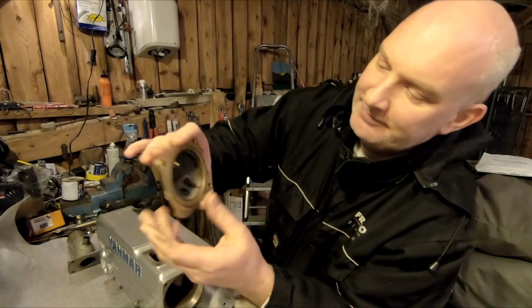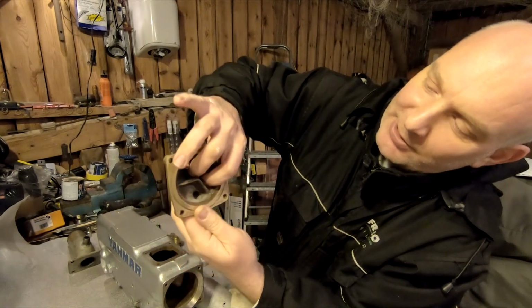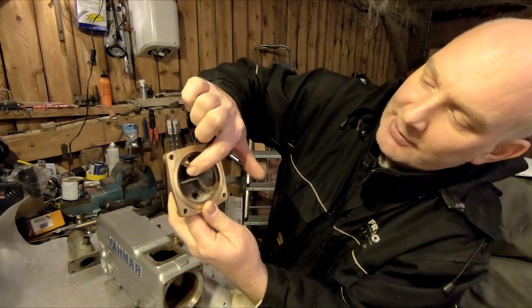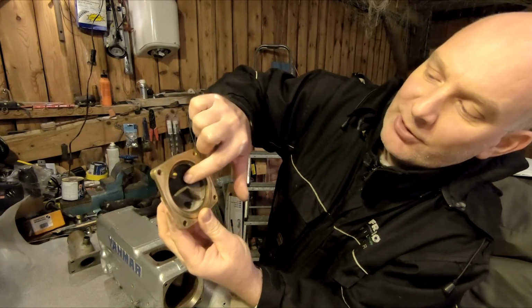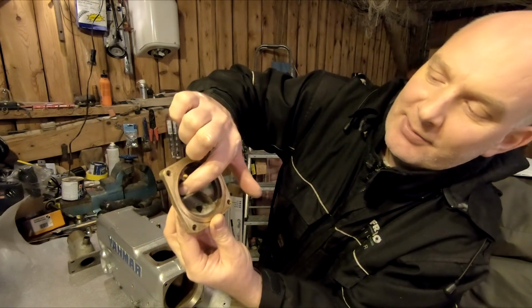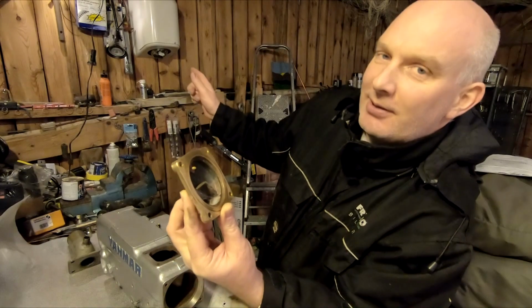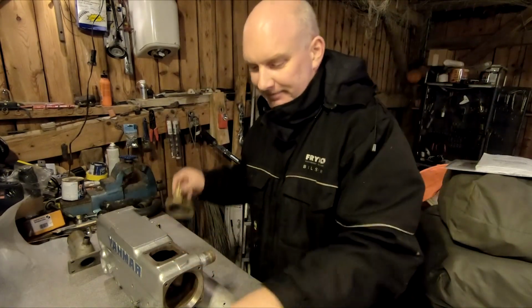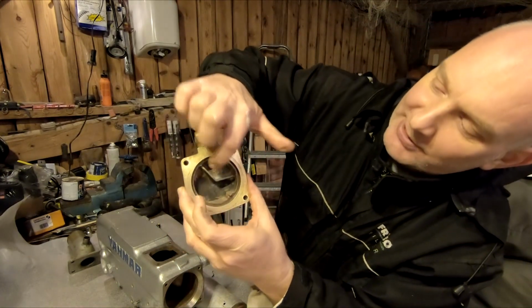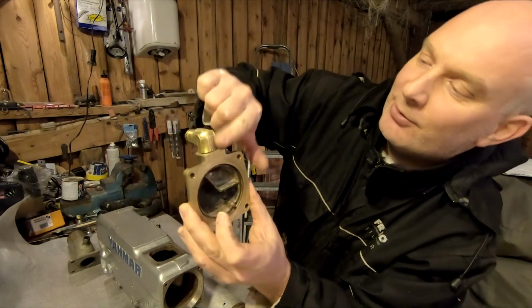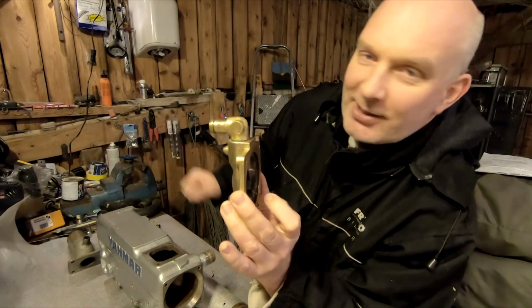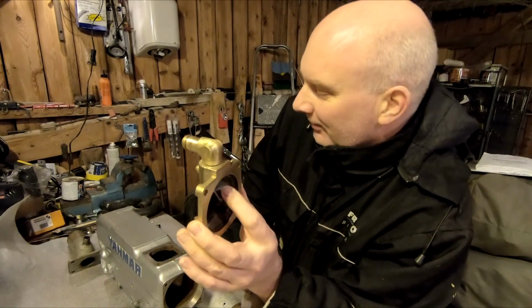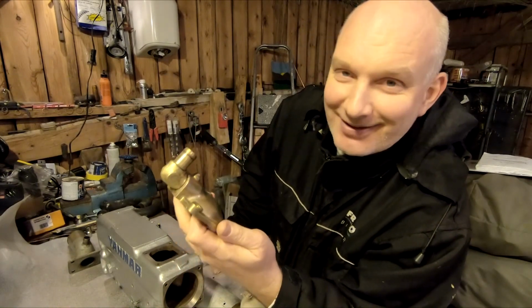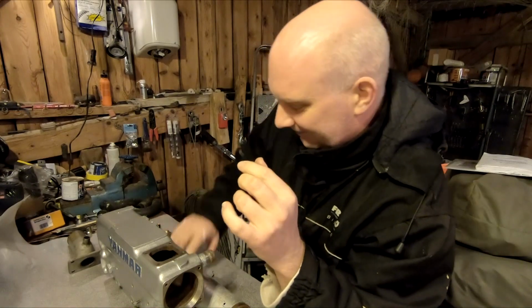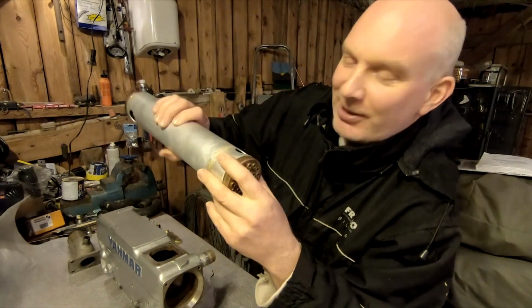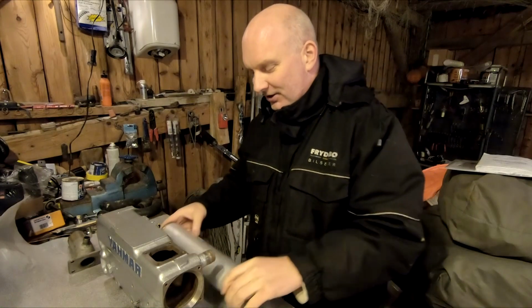And again it enters the big compartment of this lid, and has nowhere to go but to the remaining 8 pipes, returning to the other end. It ends up in this small compartment and goes out this hose barb into the exhaust elbow. So it passes 3 times through this pipe before leaving the heat exchanger.